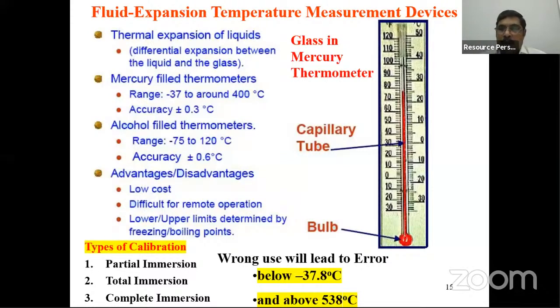And then sometimes in some thermometers, especially meant for high precision application, there will not be any marking. In that case, you have to carefully insert the thermometer till the mercury level. That is called the total immersion. And the complete immersion, of course, we are not using it. It's mainly used for atmospheric temperature, but nowadays nobody is using the complete immersion. But in the glass in mercury thermometer, you will find these two types of calibration. If you use it wrongly, then you will end up with an error. This error, even in real time, can be estimated, and there are equations available for estimating the error.